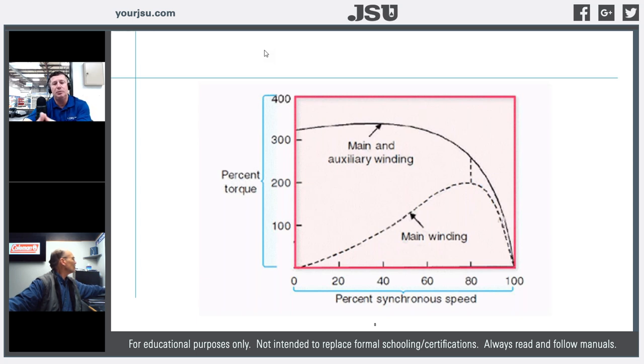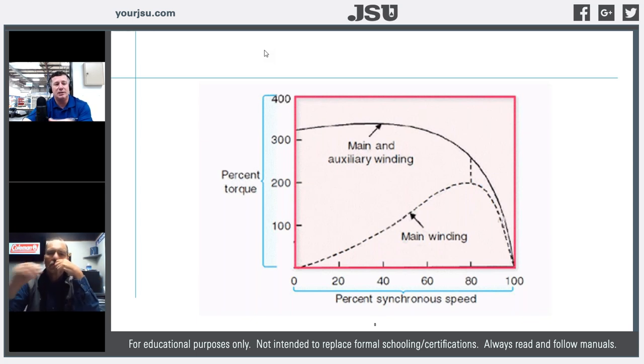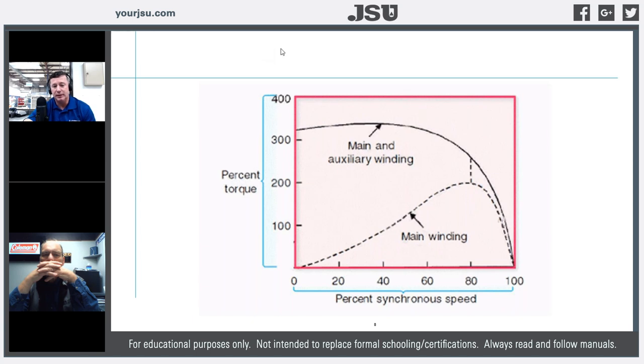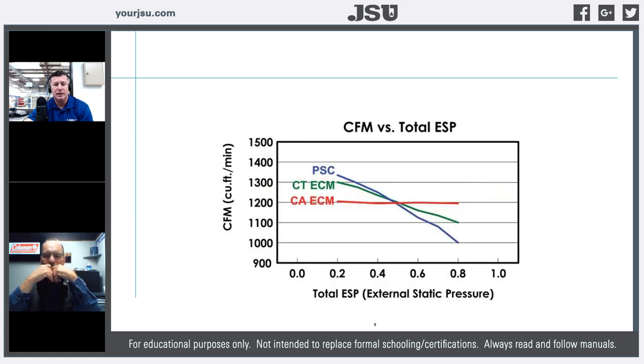We use the capacitor to assist the starting torque of our PSC motor, then keep it in the circuit so the start winding helps maintain operating horsepower torque at higher RPMs. But as we add static pressure and increase back pressure on a PSC motor and increase RPMs, we significantly lose capable torque — which is why we're starting to move away from PSC motors. But we still have them to work on, and they'll be around for a while.